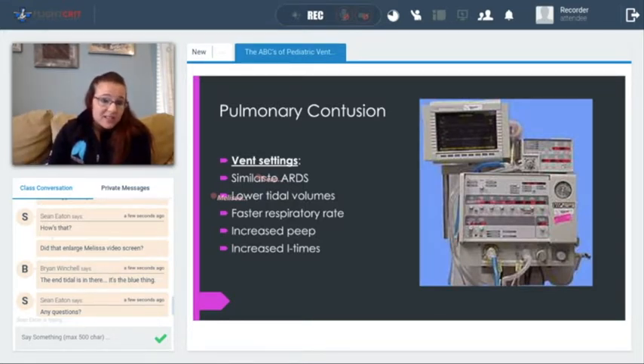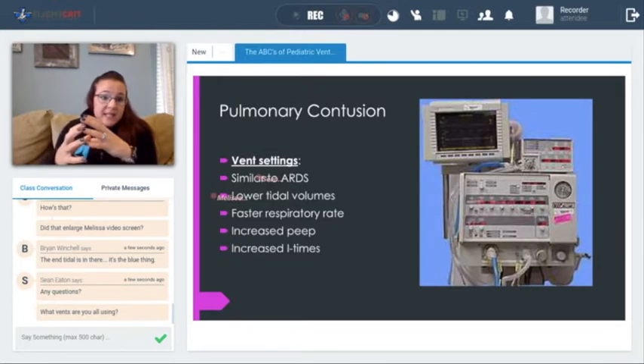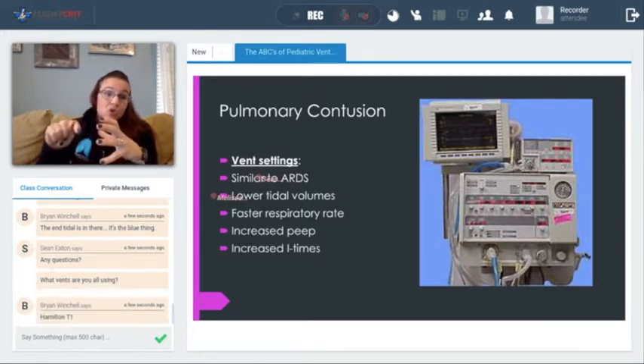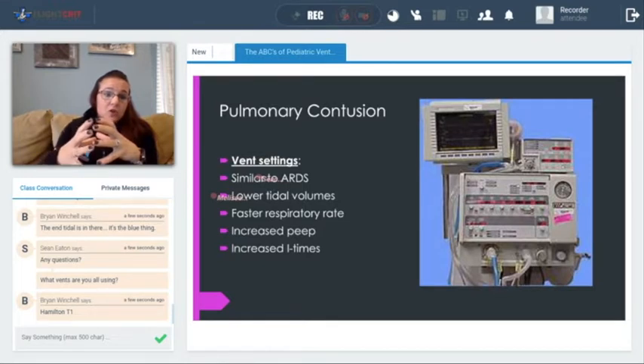And especially if you guys have a chance to set up your vent and look at this and watch what happens. So what you're going to see is, instead of that opening and closing for longer, you're going to see open, open, open, close, open, open, open, close. So think about that during that open, open, open period. That is where your PEEP is able to drive that oxygen in and push. So if you can maintain that phase of ventilation longer, you will be able to drive in more oxygen.